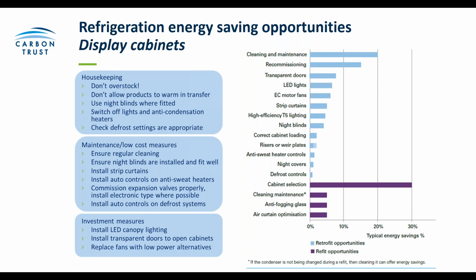You can see on the graph on the right hand side here that the most energy savings typically can be seen in this area where you are able to select the most appropriate cabinet at the beginning of the process, like a brand new cabinet. But if you're in a position where you'll be retrofitting, making sure that you have that good maintenance and cleaning and efficient use of doors is probably the biggest things you can do in terms of retrofitting and receiving energy savings.